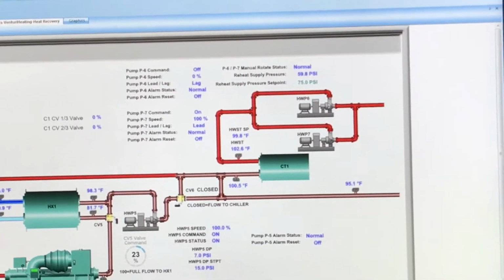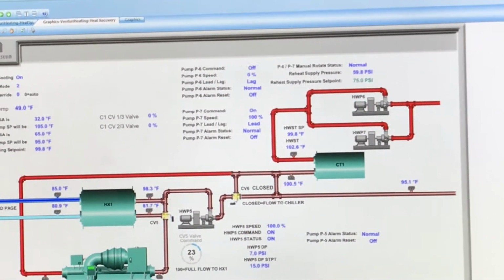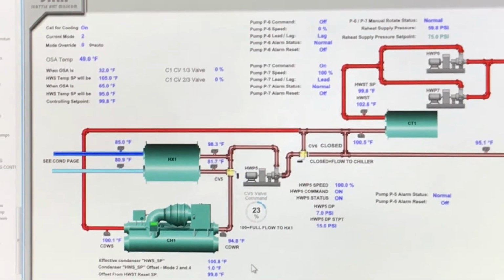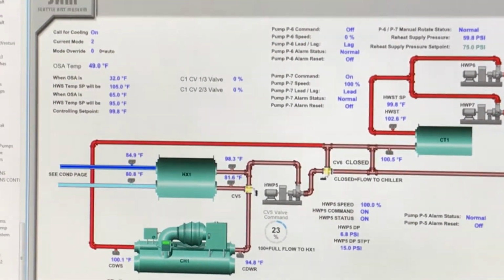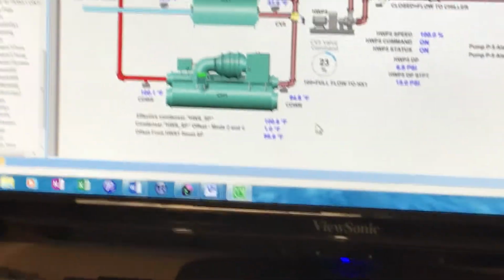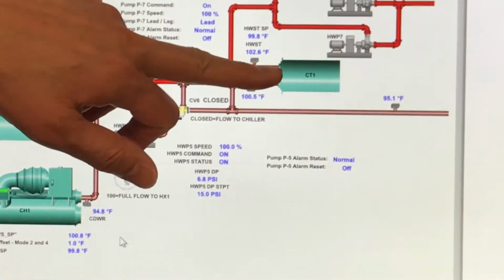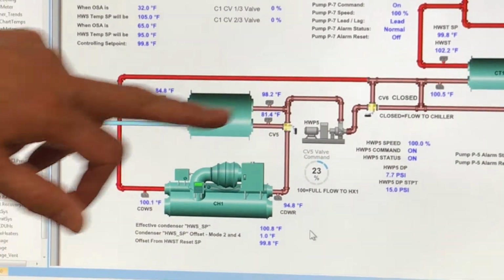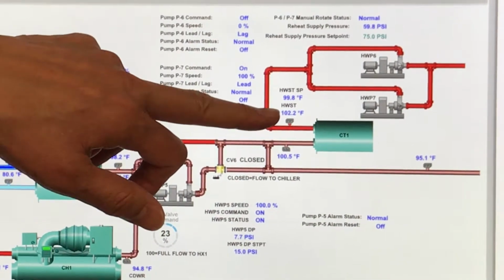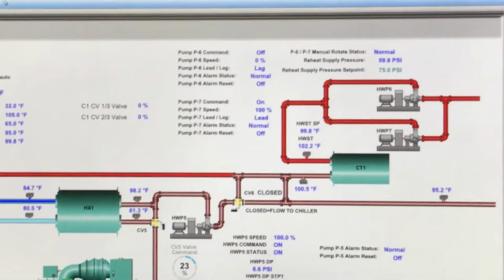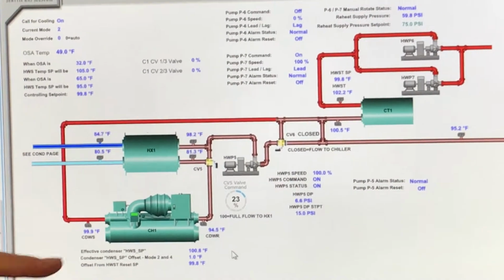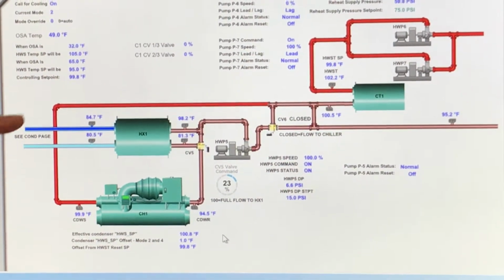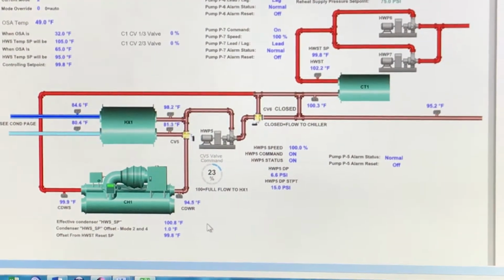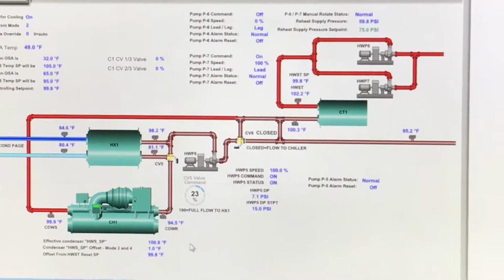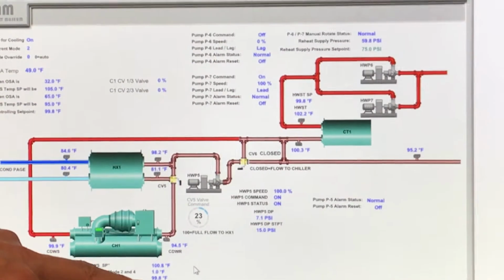And the reason for that is we are trying to get a higher leaving condenser temperature, because when you look at this, this temperature finally goes out through this converter and then goes back out, right? So if this temperature can be higher, you will be above the set point, and then the steam valve will back off. The objective is really to get this higher temperature so that you don't need to open the steam valve. Save the steam. Yeah, got it. And the offset is actually only 1 degree.